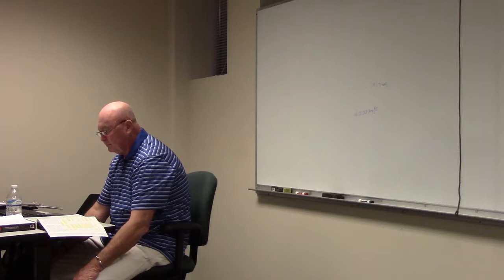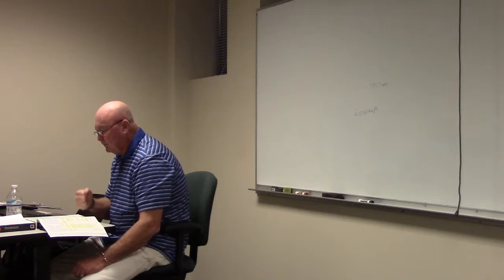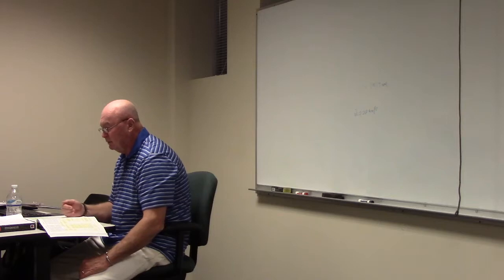Lighting loads. If I told you that it was a house, you would need to know how many VA per square foot. If I told you a 2,000 square foot dwelling, how much would the VA be for the lighting? 6,000, right? So know how to do that. Understand how to do that.